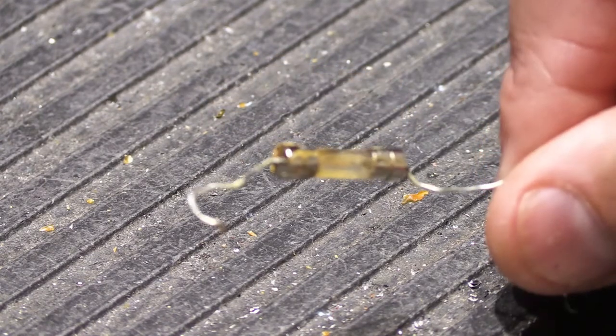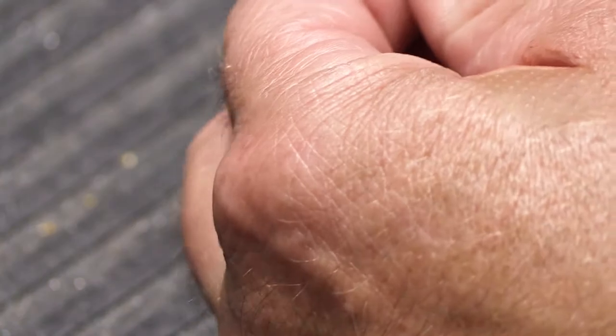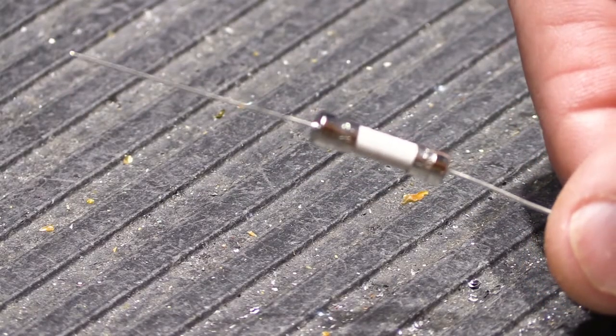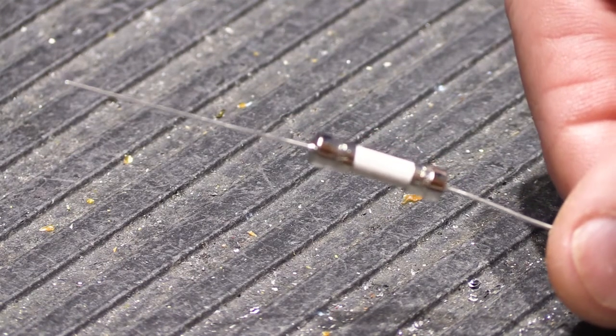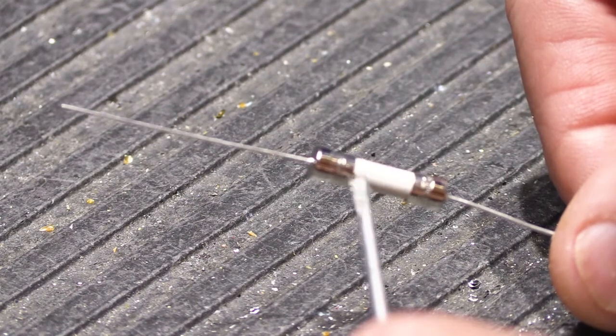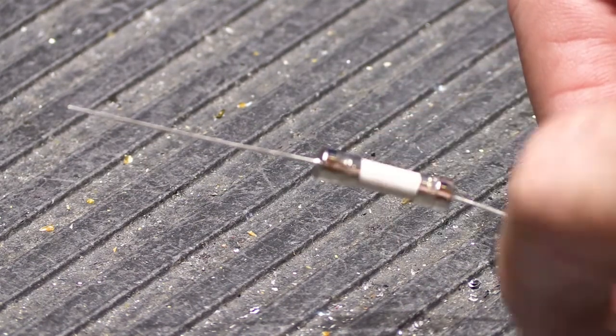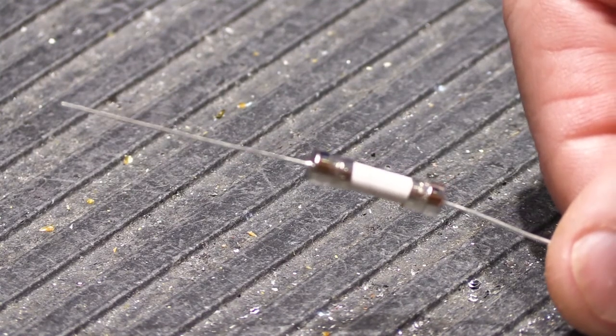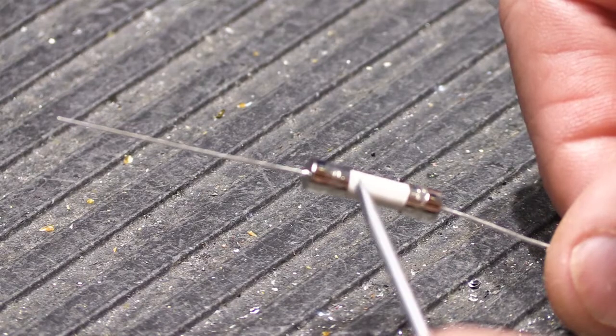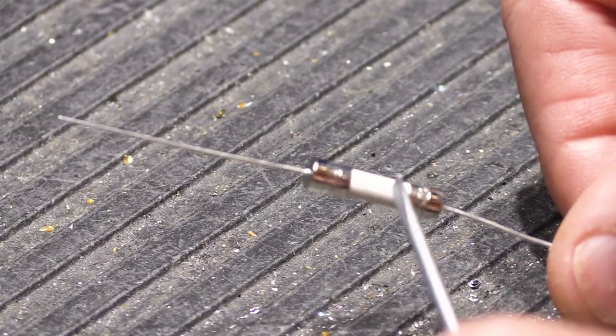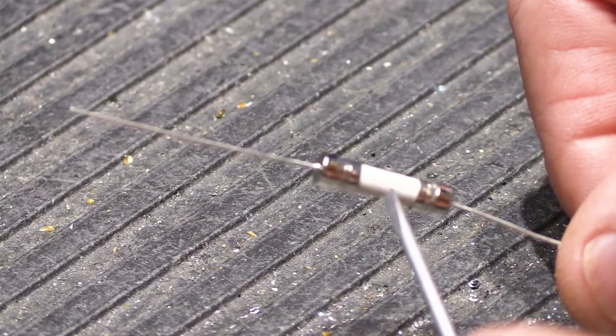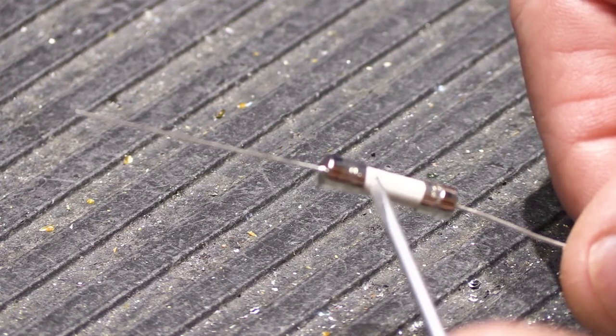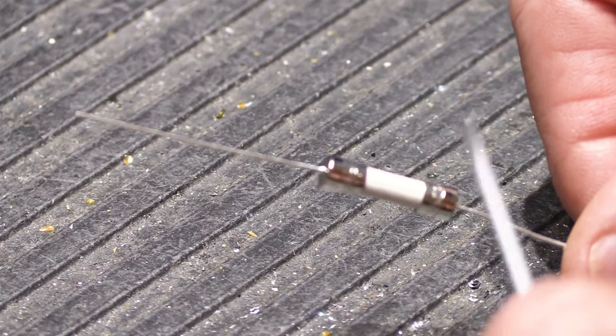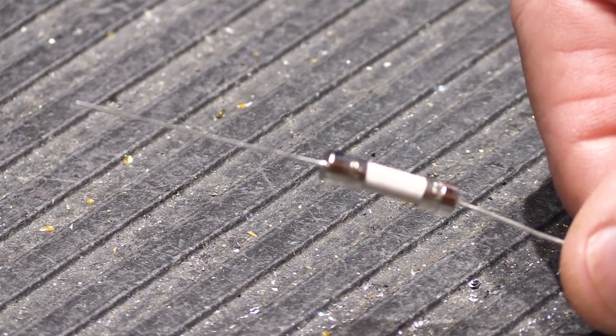We're going to replace this with something similar, but in my opinion a little better - one of these. This is also an axial lead cartridge fuse, but it has a ceramic body instead of a glass tube. The body material doesn't really affect how the fuse acts or blows - it mostly comes down to the fact that this is a sturdier physical construction than a glass tube. It costs a little more than a glass fuse, but we're only talking about a few cents, so it doesn't matter. I think it's better to have a sturdier fuse if we have to bury it down inside the tape of the transformer.